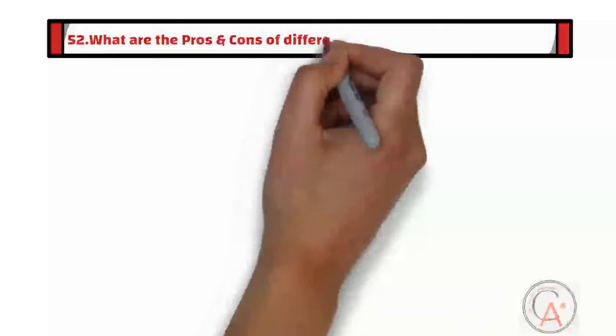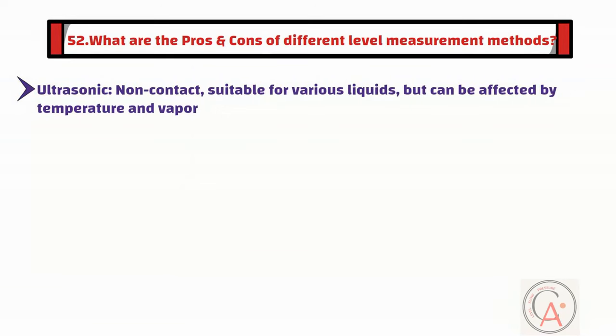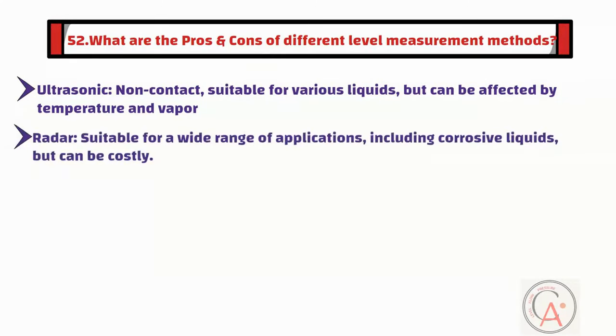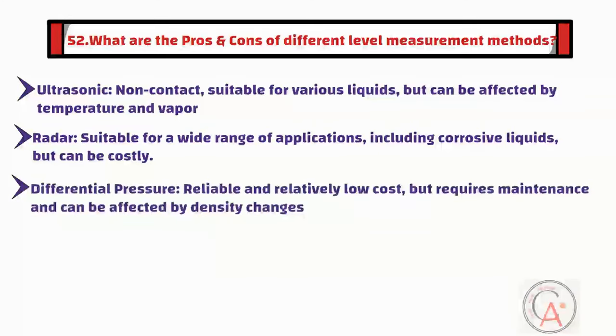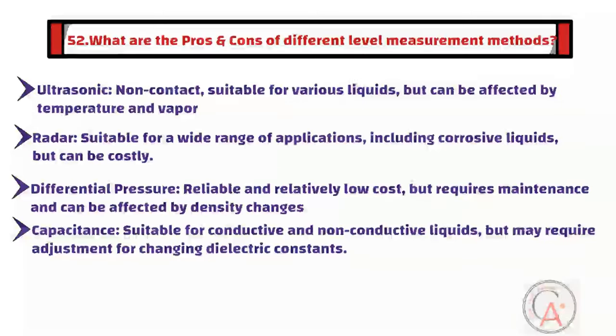Question fifty-two is: what are the advantages and disadvantages of different level measurement methods? Each level measurement method has its own set of advantages and disadvantages. For example, ultrasonic is non-contact and suitable for various liquids but can be affected by temperature and vapor. Radar is suitable for a wide range of applications including corrosive liquids but can be costly. Differential pressure is reliable and relatively low cost but requires maintenance and can be affected by density changes. Capacitance is suitable for conductive and non-conductive liquids. The choice of method depends on the specific application's requirements and conditions.